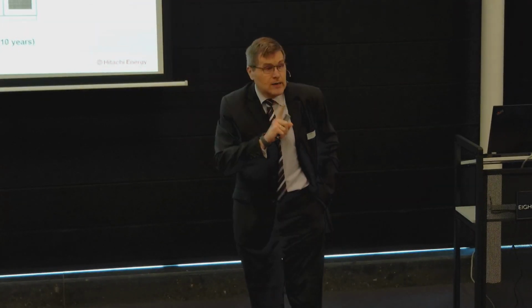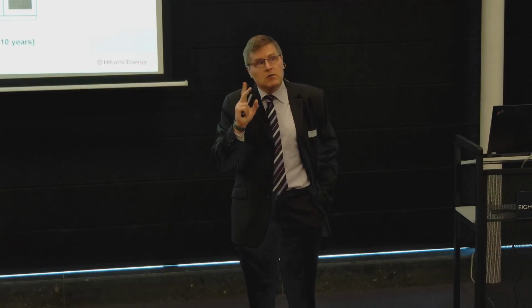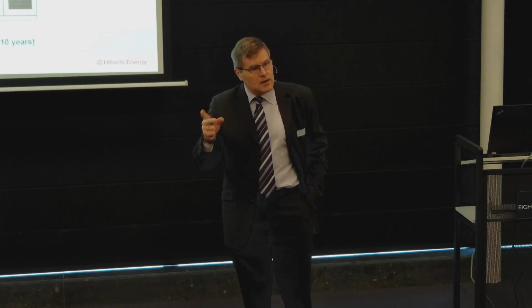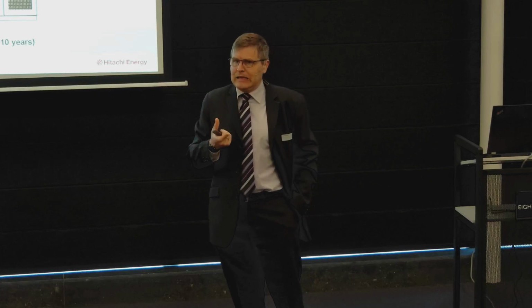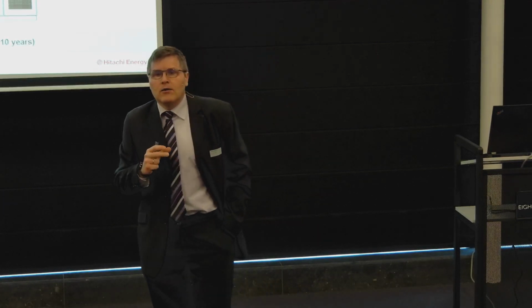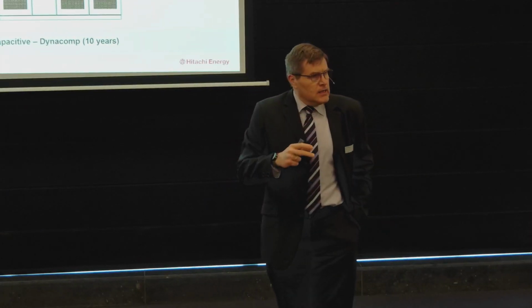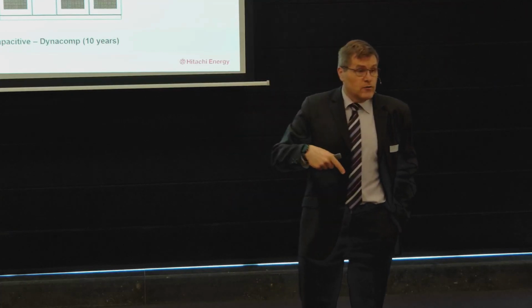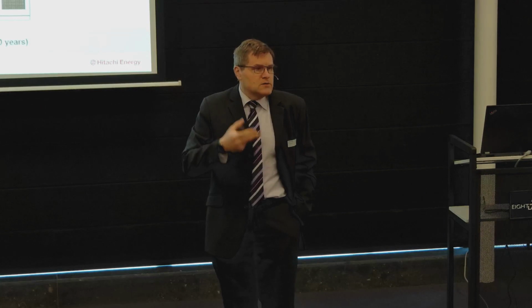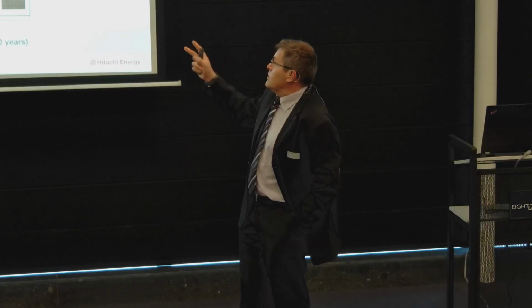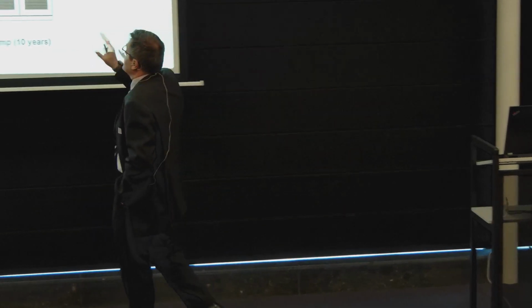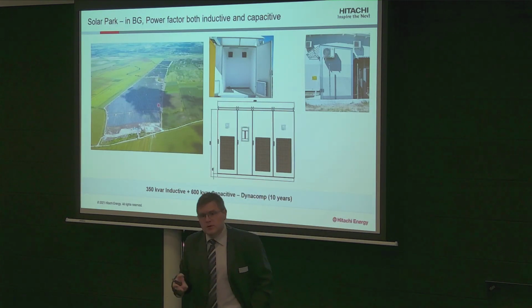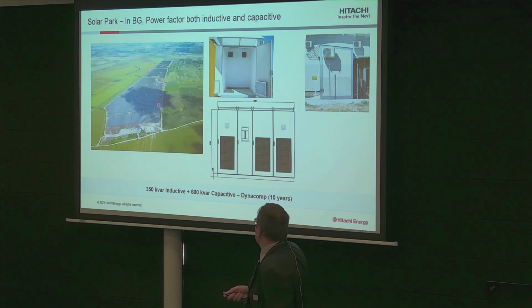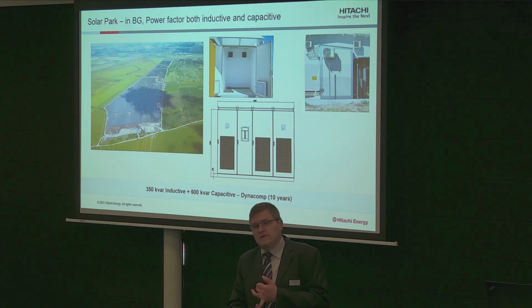But here, during the night, we were talking about, let's say, 300, 400 kVAr of capacitive energy. So then it was not negligible, 340. So it's half a MVA of load. So then the utility here imposed to do something. And during the day, the power factor was not so low, 0.92, 0.93, but we needed about 600 kVAr. So here we proposed a special capacitor bank with both capacitive and inductive called Dynacomp, a dynamically controlled capacitor bank. Alors, yeah, here it was in the middle of the countryside, so we had an IP50 rating. We had to do an anti-snow building with air cooling and so on.